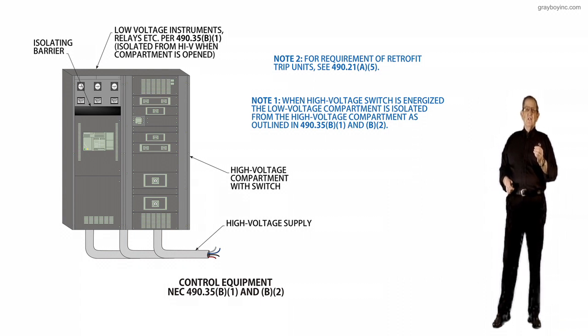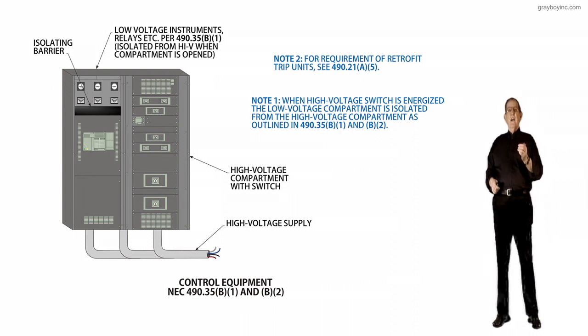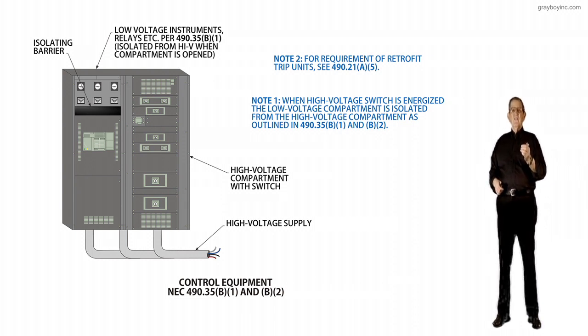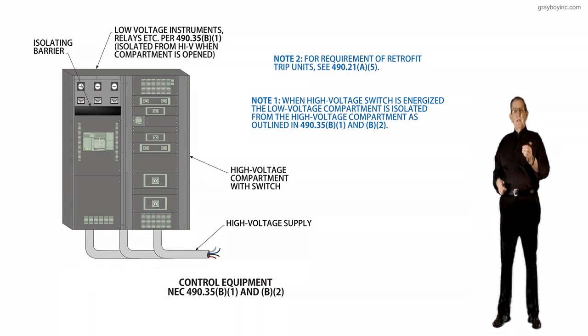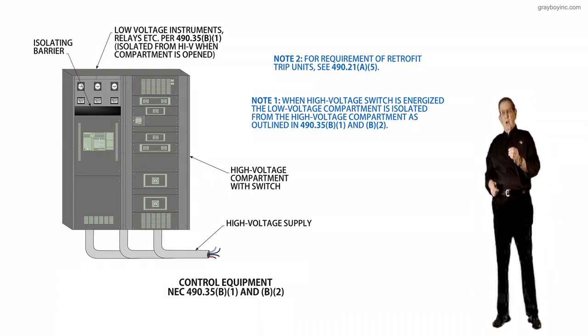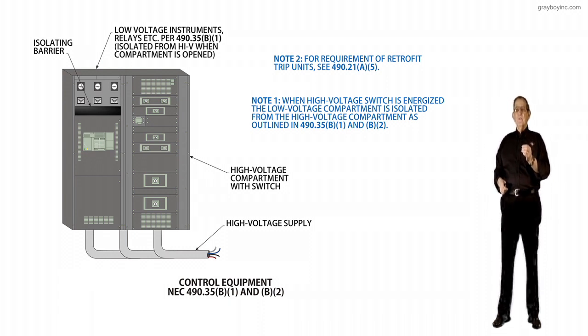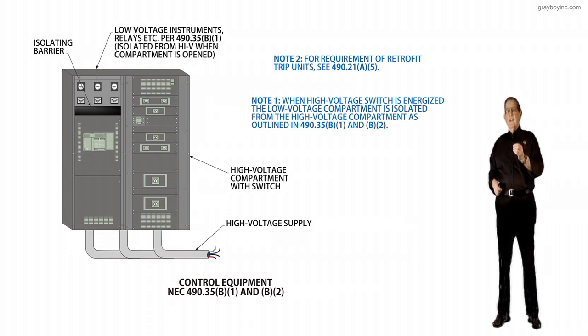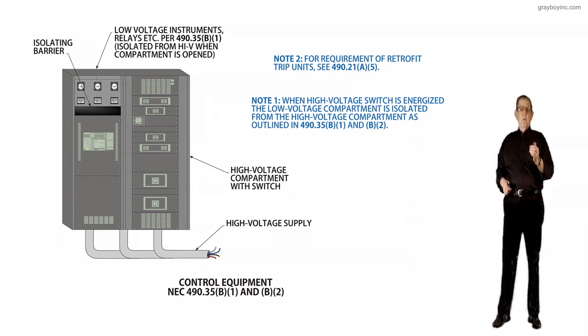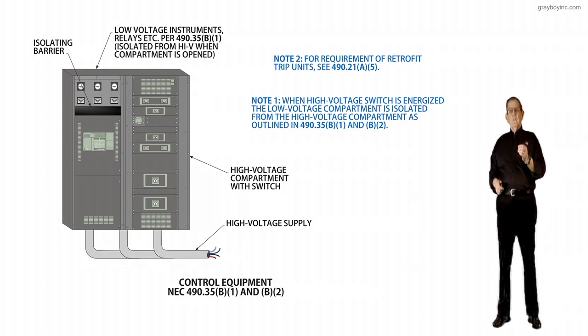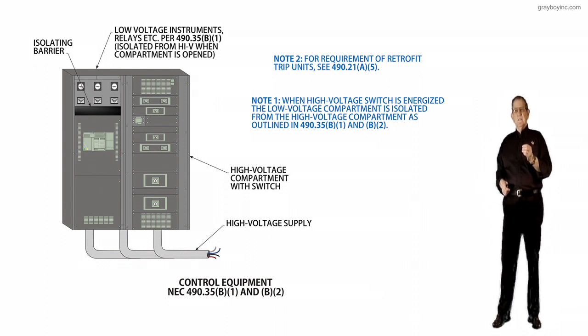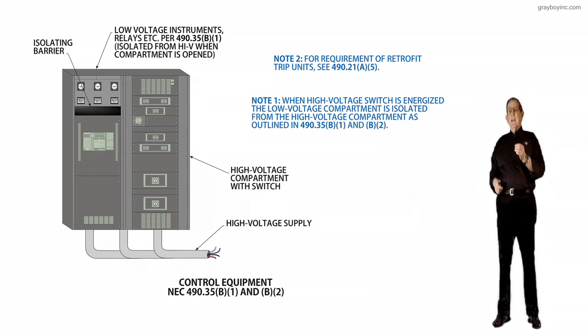The section 490.35 B of the 2017 National Electrical Code offers two conditions that will allow low voltage components to be installed in compartments having exposed high voltage energized parts or wiring. But these two conditions are interrelated and should actually be stated as one.